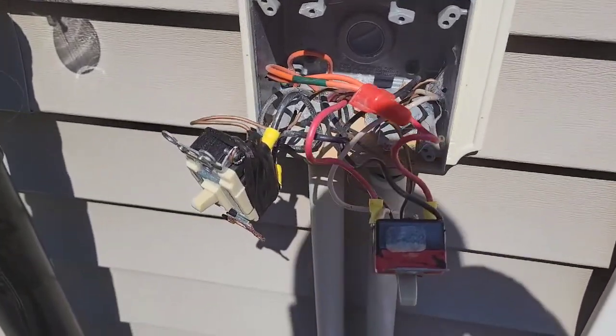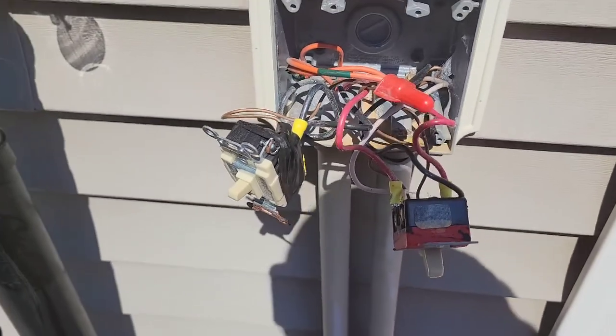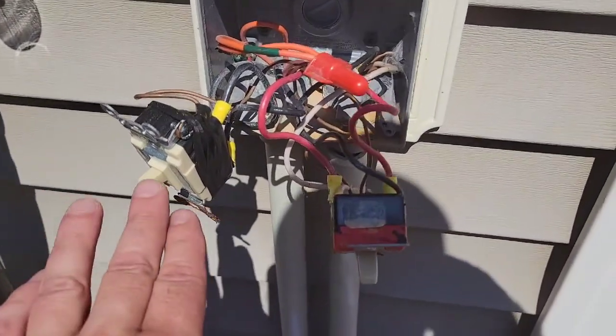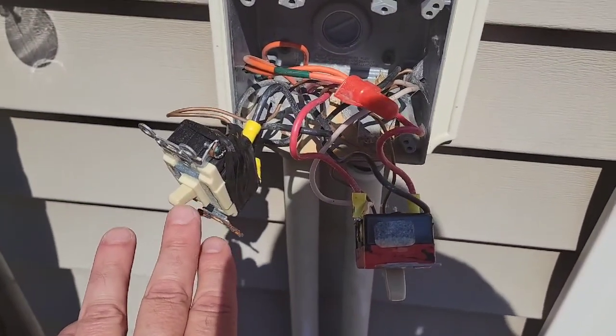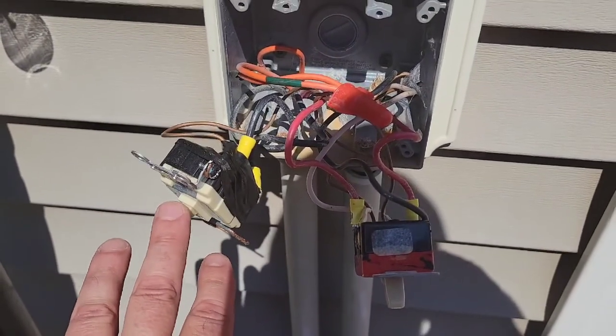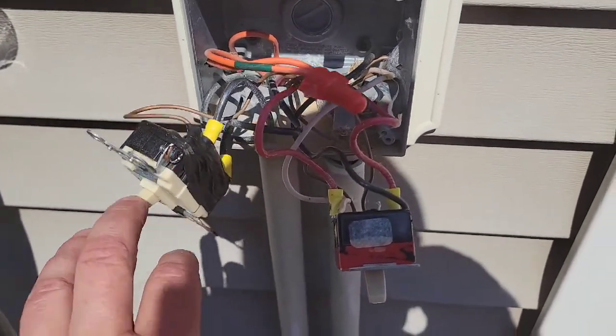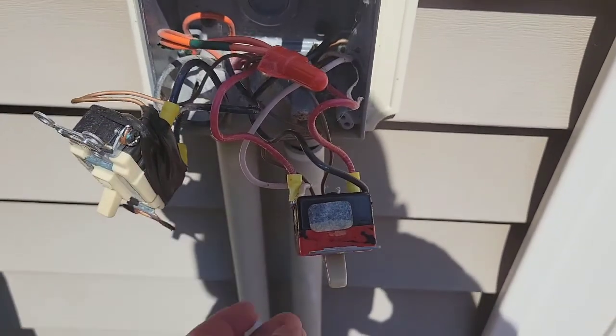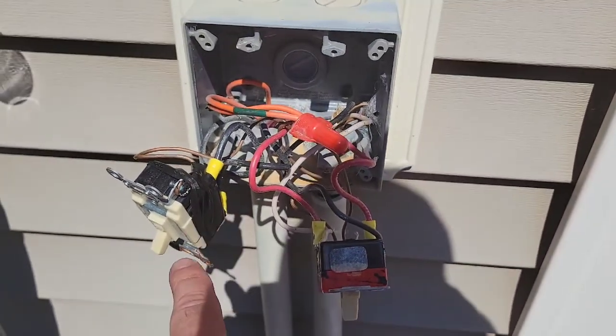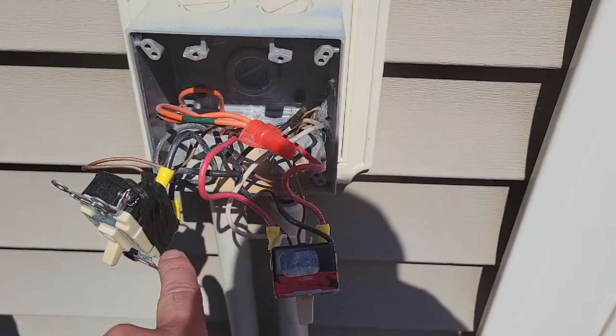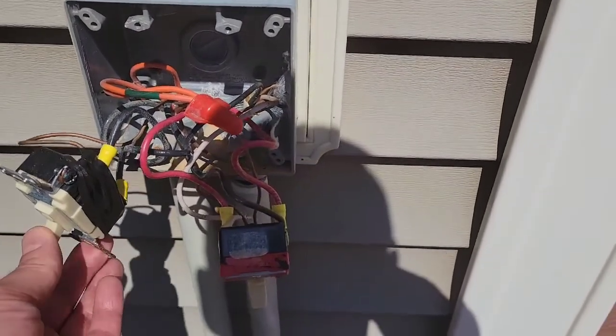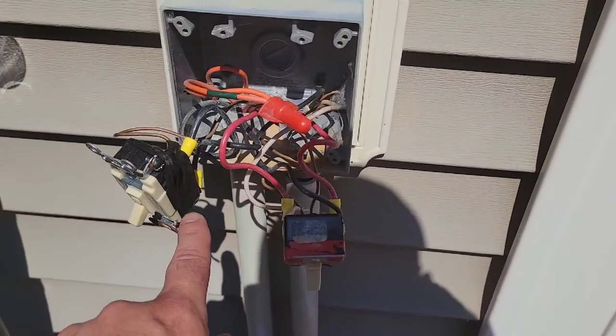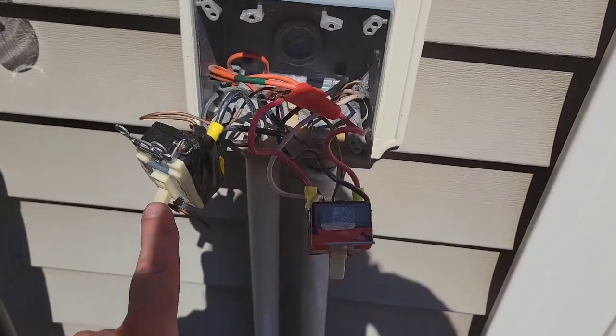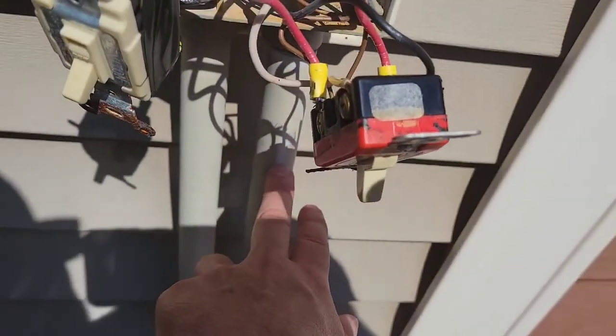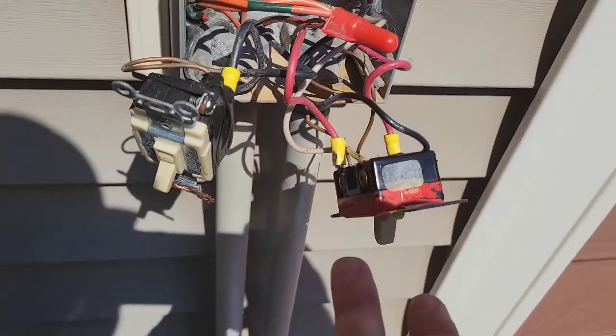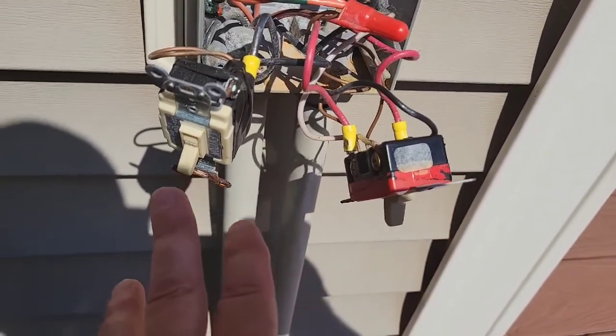I wasn't 100% sure, but we did have a source problem in the end. So this was a 120 volt circuit. We checked that out, and it was 120 volts in the off position from the source side, and when we turned it on, the load side did indeed have 120 volt sources on it. But I was confused because the house wiring is coming from this other side, and that's when I started scratching my head as to what was really going on.